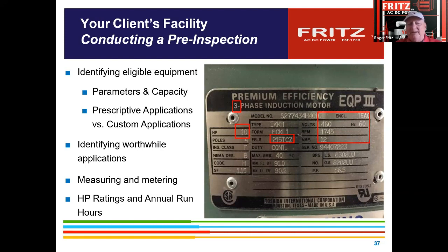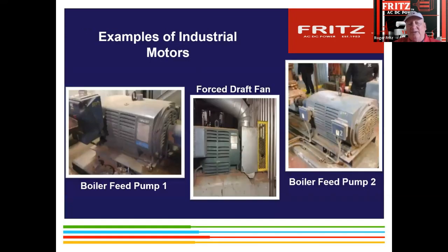But we've run into facilities where they went to bid, looked at the application, got it all installed, everything was to spec, but somebody didn't look at the RPM ratings. And now they literally cannot run those motors over 50 Hertz, or they'll trip out all the time. They just have too much amp draw, and it caused a little grief. They're getting around it, but it's not the best way to do it.